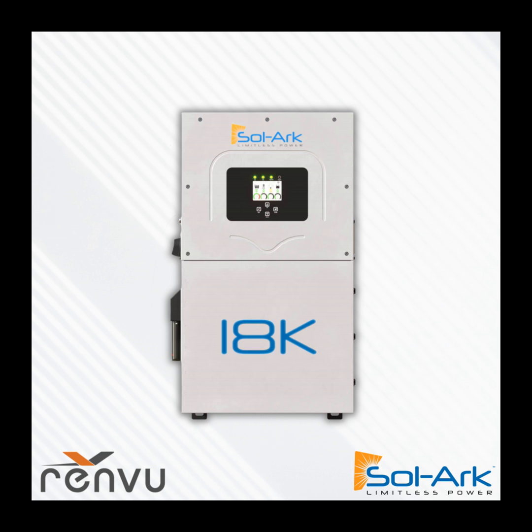Fundamentally this is just an enhancement of our 15K. Now, we'll cover the spec sheets and details, but what this means is you're going to get a larger solar array, the same number of solar inputs, but more amperage, so it can better accommodate bifacial solar panels and parallel strings. The DC input voltage of 500 volts is the same — a little lower than a traditional string inverter voltage of 600 volts, but with 3 MPPTs, what you get is maybe a little shorter strings, but it's a string inverter, and shorter strings mean better shade mitigation and management without having to do optimization at the module level.